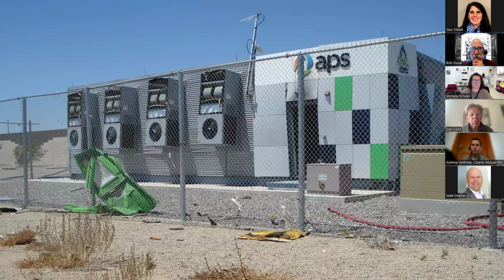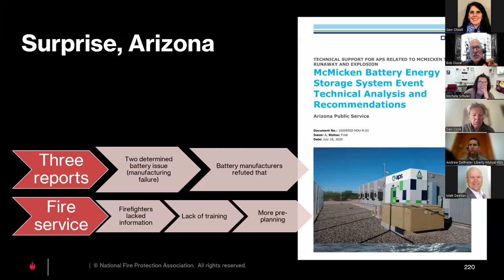So this is the enclosure, and that was the door they used to go in. You can see the whole thing is off kilter now due to the pressure of the explosion. We don't have time to go over the media accounts, but there were several reports done by the utility and by Underwriters Laboratories, UL. I went out and met with the fire department and responders to make sure our standard 855 had enough provisions to prevent this in the future. This enclosure wasn't built to that standard because it wasn't out yet at the time of the incident.